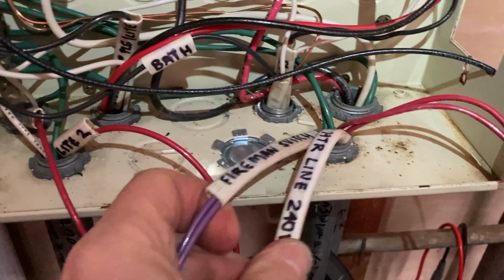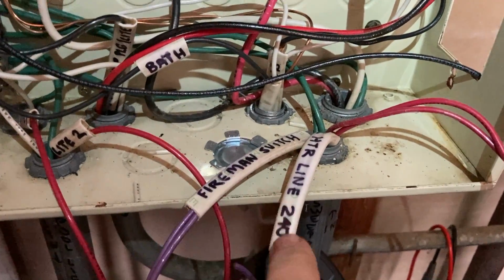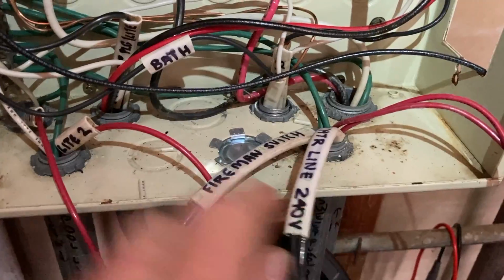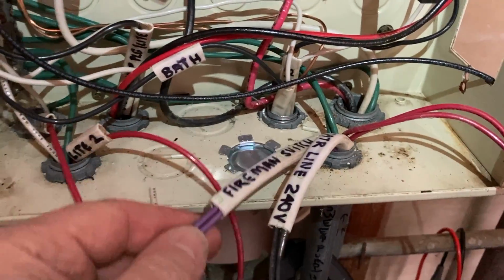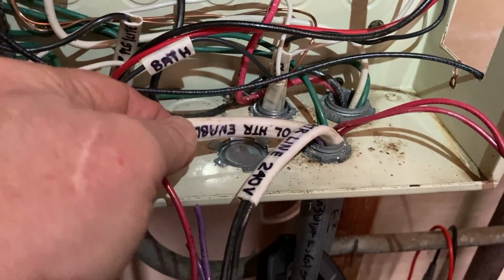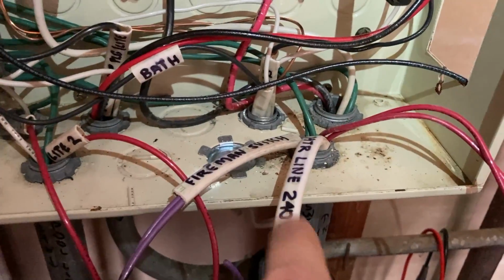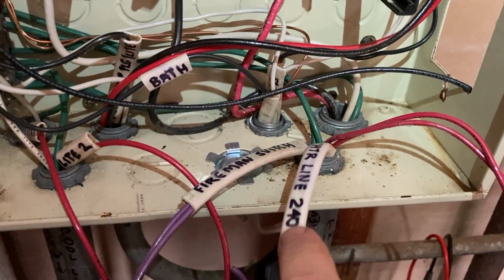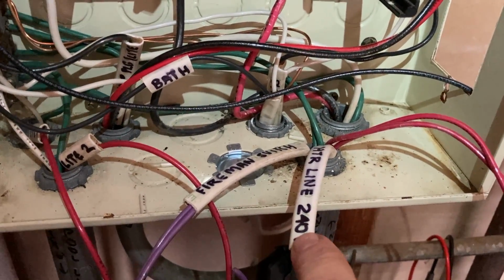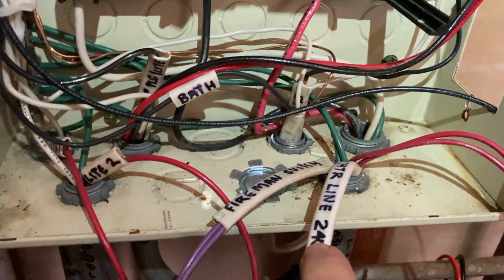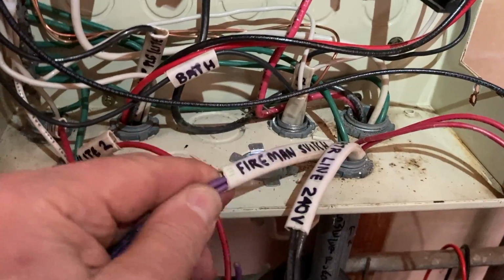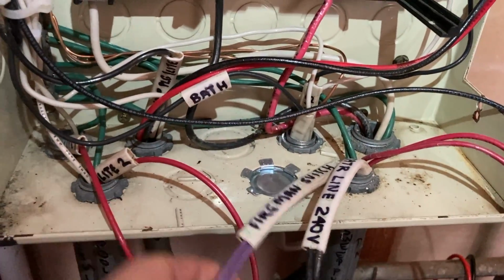It was interesting to find out that you have a 240 volt line that's on all the time, and then this other thing connected to the auxiliary switch on the timer - that's a fireman switch, a dead man switch. So the pool boiler furnace always has 240 volt power for its electronics, but it can't ignite unless this switch is closed, and that's what the aux switch was closing.